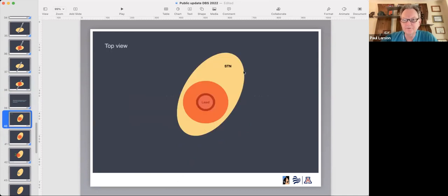So we're going to look sort of top down. Again, this yellow structure is what we want to stimulate. The lead is the stimulating electrode, and this black ring is the metal ring that we're stimulating. This is what historically we've done. The stimulation encircles the electrode, so it's spreading evenly in all directions. And if the lead is right in the middle of the target, we're in good shape.